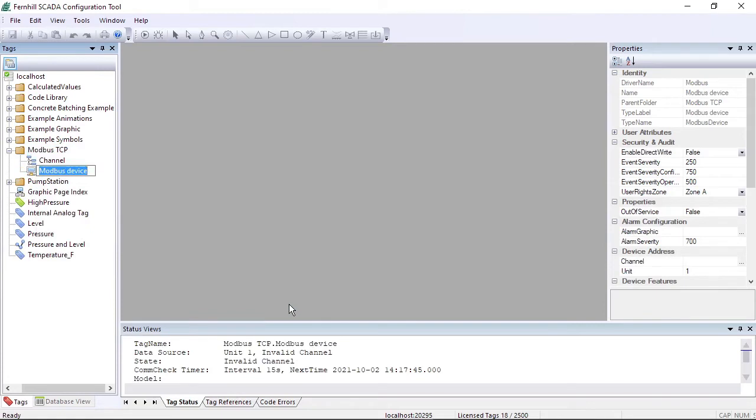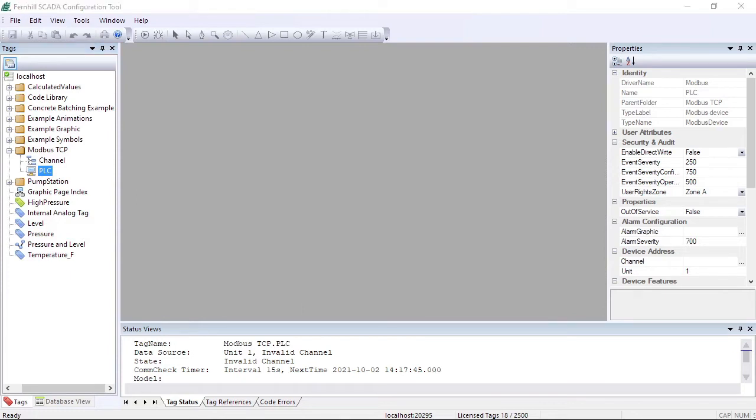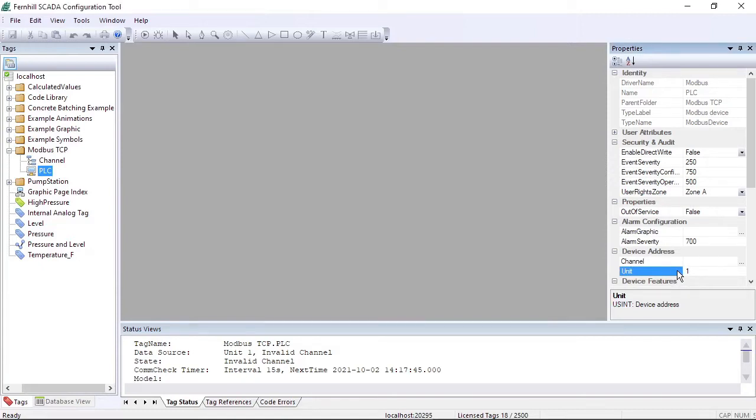Shorten the tag name to PLC and press Return. You might need to configure the Unit property of the PLC device tag. Whether you need to depends on the type of Modbus TCP device you are using. For example, some Modbus TCP devices ignore the unit number, while others require a specific value.